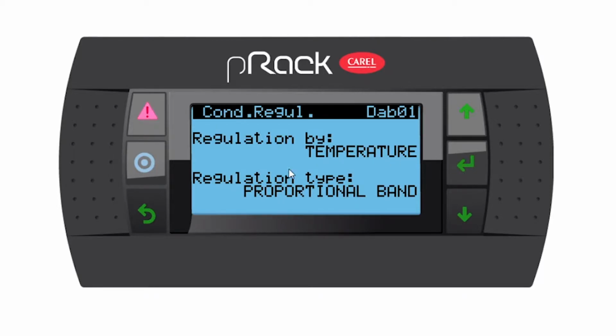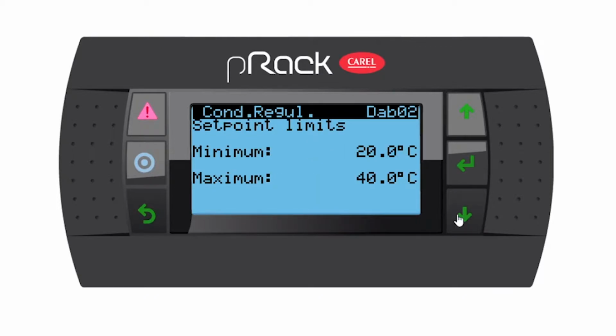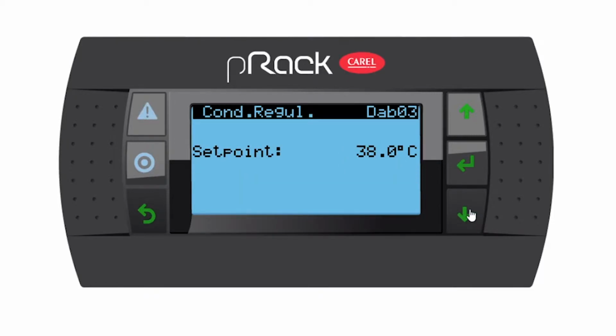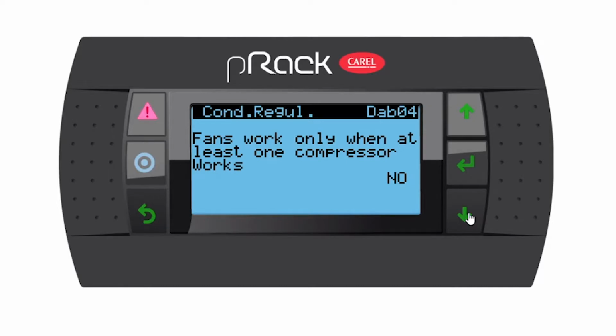Regulation by temperature and proportional band, yes, because that's how we did the wizard setup. So let's go down, set point limits. So here you can limit your end user within a certain range from your set point. So that's where you do this. So let's go down. The actual condensing set point of 38 degrees Celsius. Perfect, let's go down. Fans work when at least one compressor works, no.